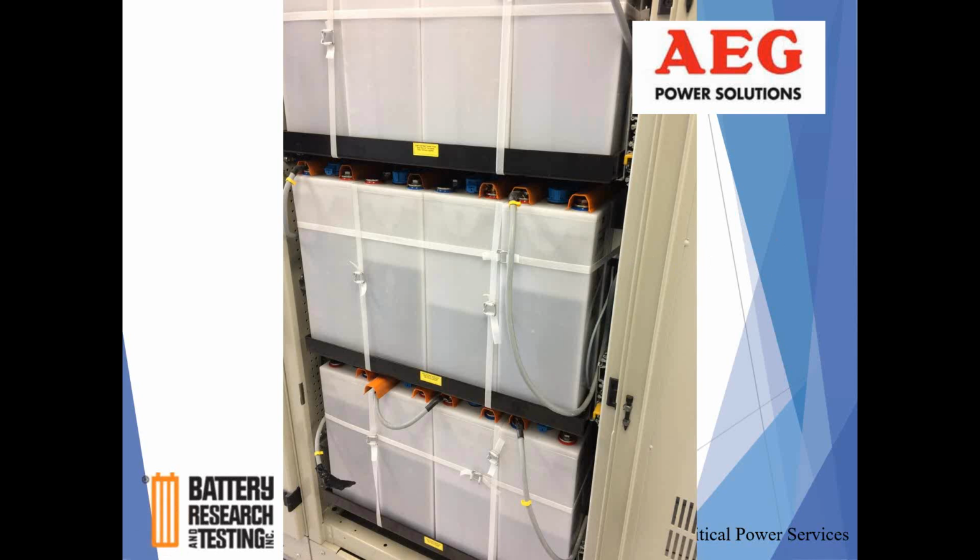Hey, phantom alarm, we know there's an alarm going on here on the system. You walk into the room, that red or amber LED is lit. It's lit all the time. So if you have a general summary alarm on the system, you don't know to really look for it. It's like, oh yeah, that thing's always in alarm. It's not a problem. That's because of the sensor.